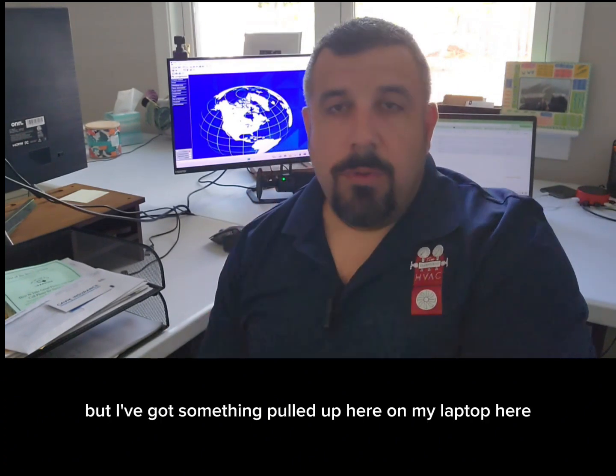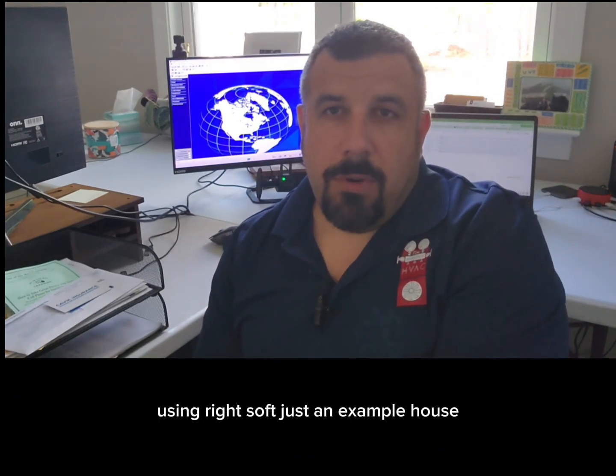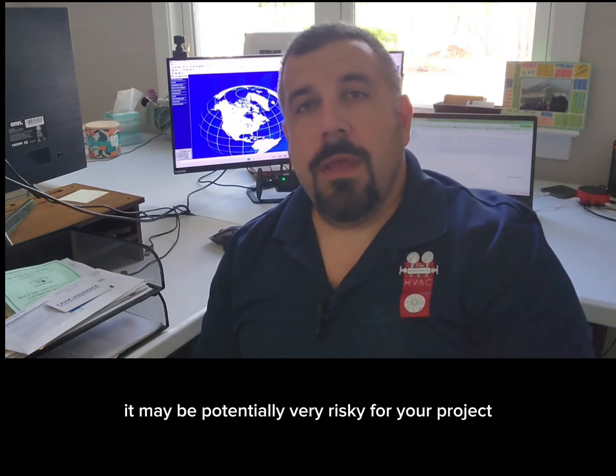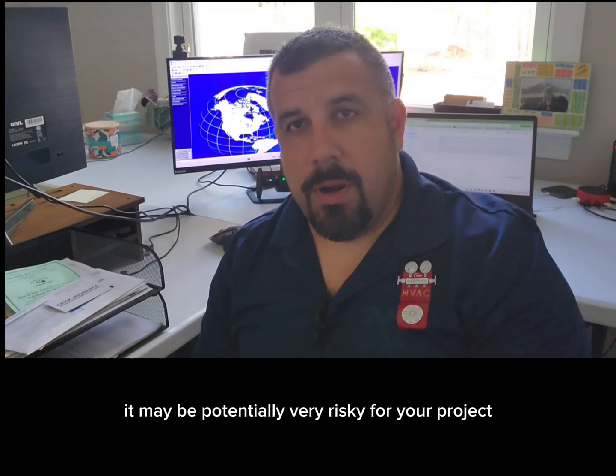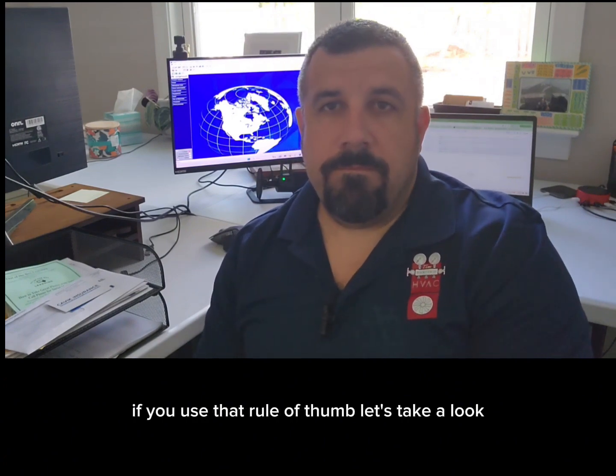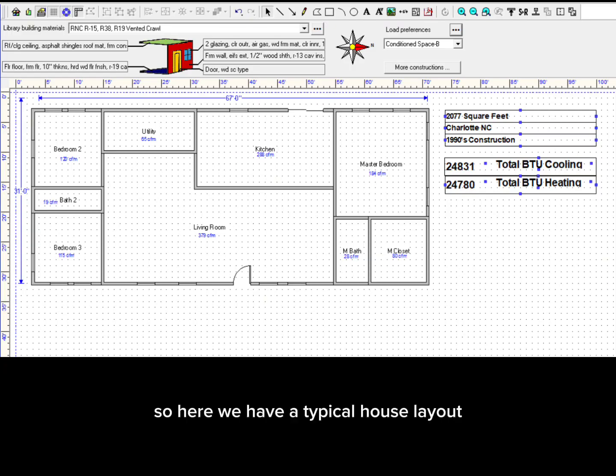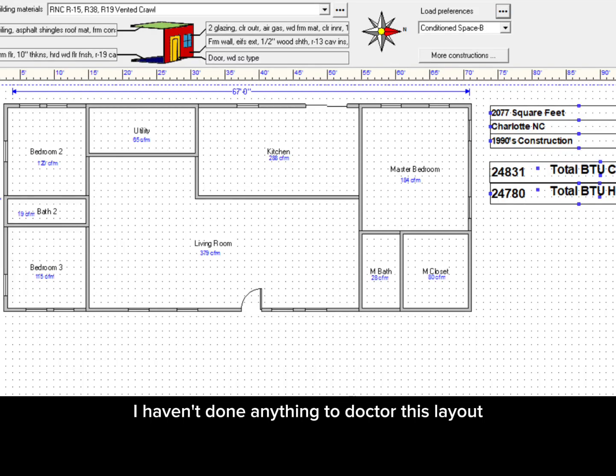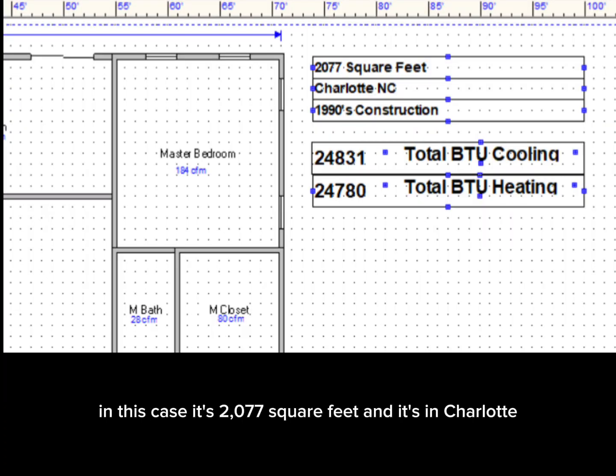But I've got something pulled up here on my laptop using RightSoft, just an example house. And I'm going to show you why it may be potentially very risky for your project if you use that rule of thumb. Let's take a look. So here we have a typical house layout. I haven't done anything to doctor this layout. This is your typical ranch house that we see everywhere. In this case, it's 2,077 square feet, and it's in Charlotte, North Carolina, 1990s construction.